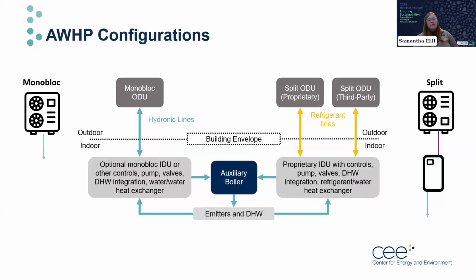Looking at the schematic again, taking a closer look on exactly how those systems are different in terms of monoblock versus split. In the monoblock case, all of the important stuff that makes up the bare minimum of an air-to-water heat pump lives outside in a rather large box, and it's only hydronic lines, water lines, that penetrate the building envelope. And these monoblocks, even though everything you really need is outside in the outdoor unit, often have optional indoor units that comprise pumps or valving or controls that simplify the installation, making it so that there's less connections to make indoors. So a monoblock system sometimes still has an indoor system, but it doesn't necessarily need one. And the key characteristic is that it's water lines that are going into the building.